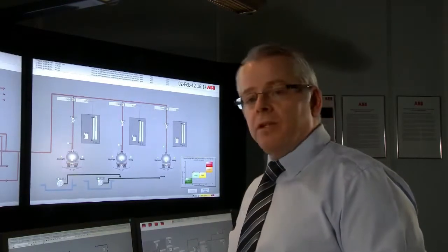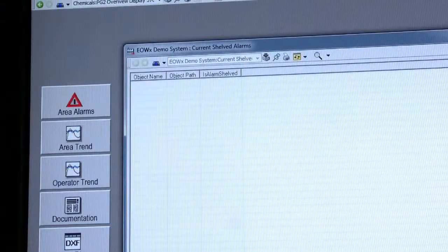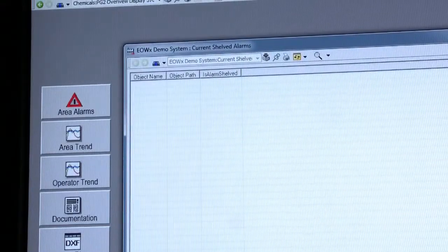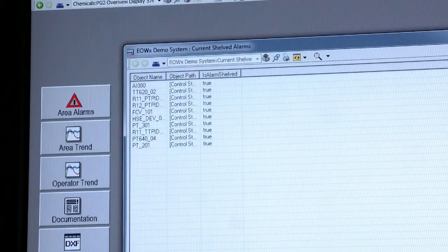Another way to access hidden alarms is through a new feature within 800XA called Snapshot Reports. Snapshot Reports can simply generate a list of any property within 800XA — in this instance it's shelved alarms, but in other instances it might be set points, or any safety systems in override, inhibit, or manual.